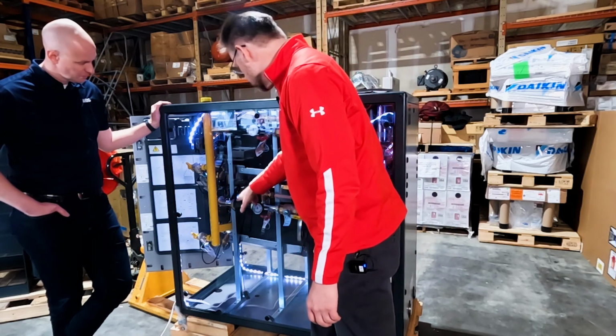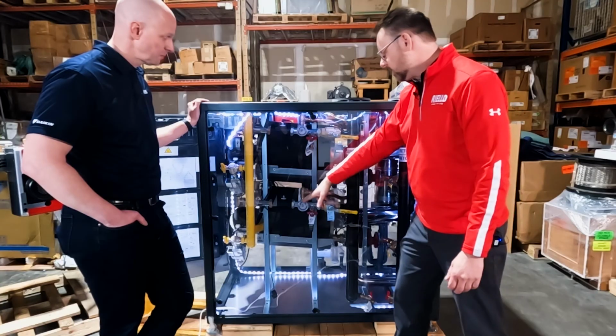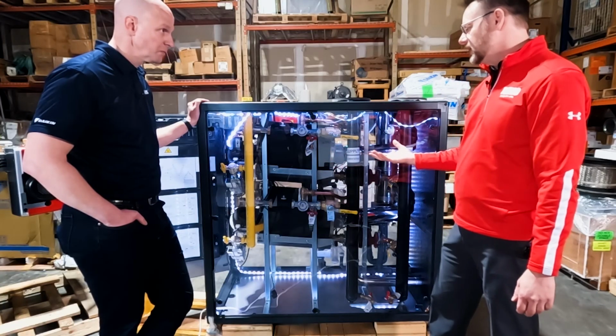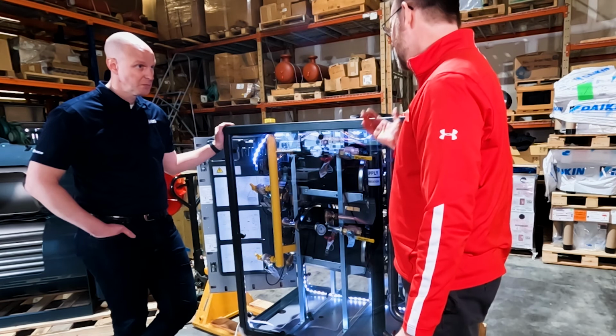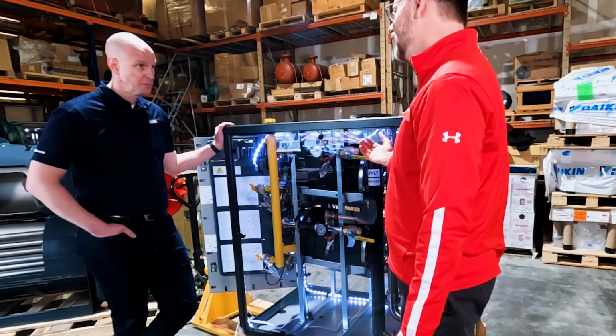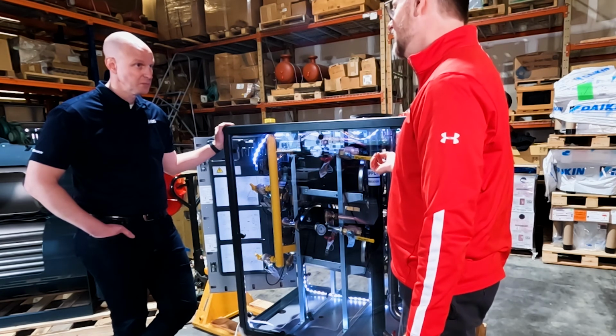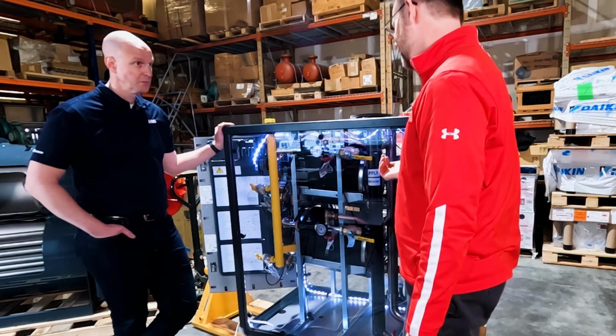From this side, we also get to see the flow meter—these black devices here. We use a flow meter so we get a true gallons-per-minute output that's harder to jumper and deceive than a flow switch, because it may not be convenient in the moment to fix a flow switch.